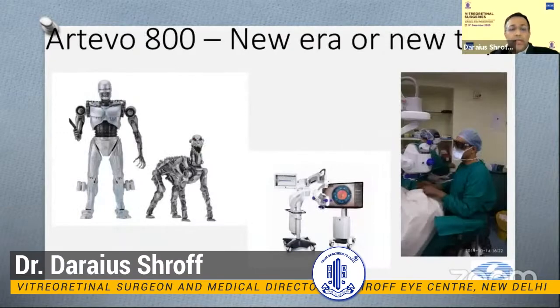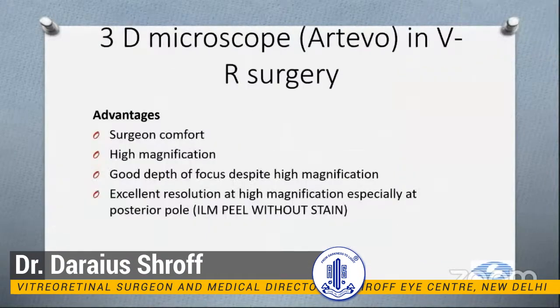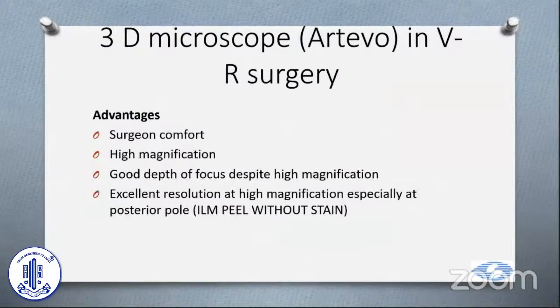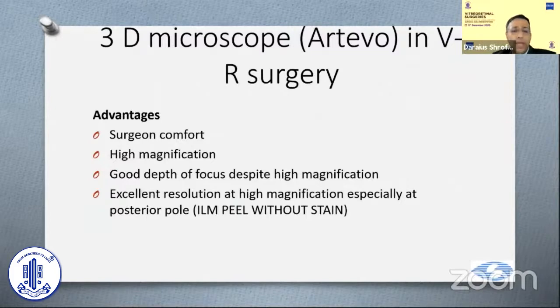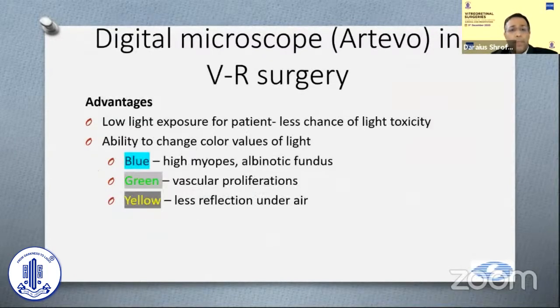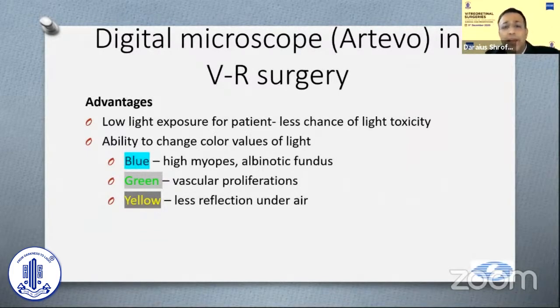The Artevo 800 — is it a new era or a new toy in our armamentarium? It has definite advantages: more surgeon comfort as Dr. Natarajan showed, higher magnification, good depth of focus despite the magnification, and excellent resolution with high magnification especially at the posterior pole. A big advantage for patients is low light exposure, so less chance of light toxicity, and you can change the color value of the light used while operating.